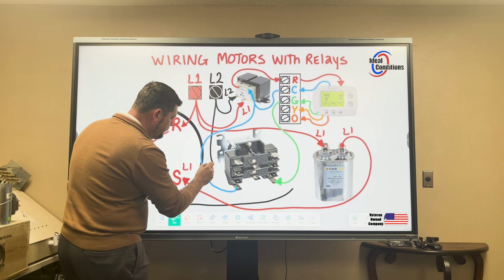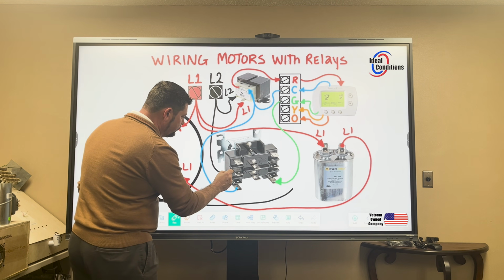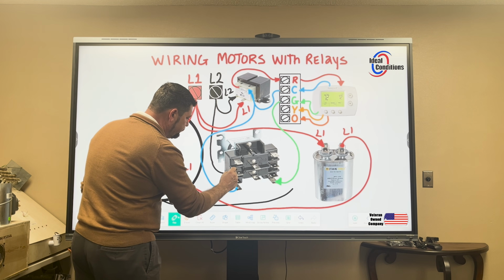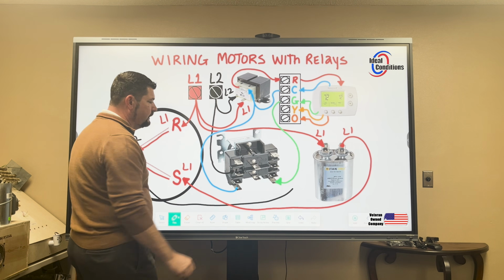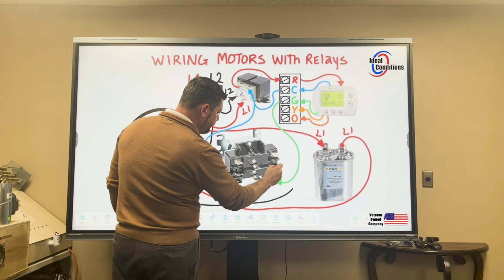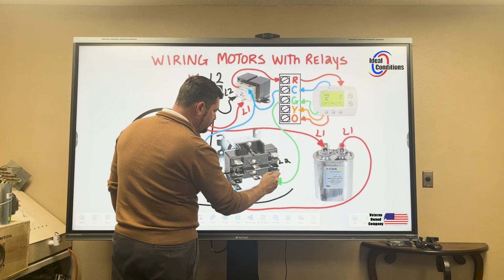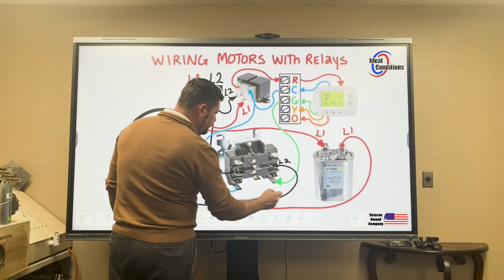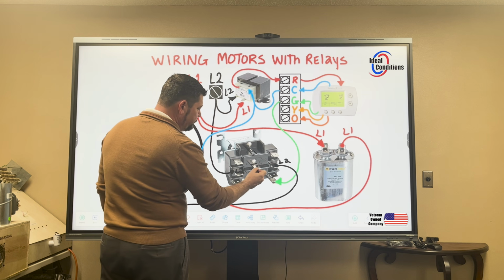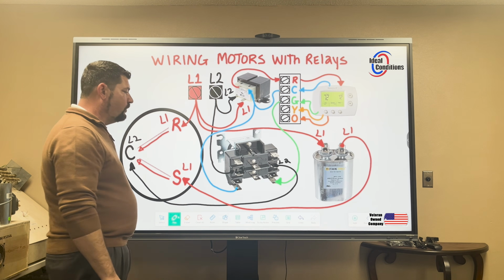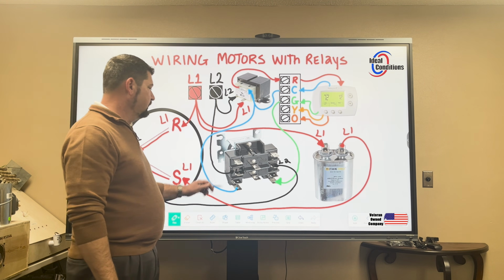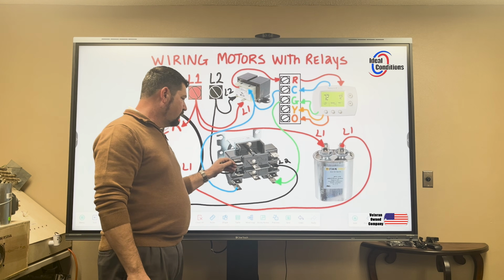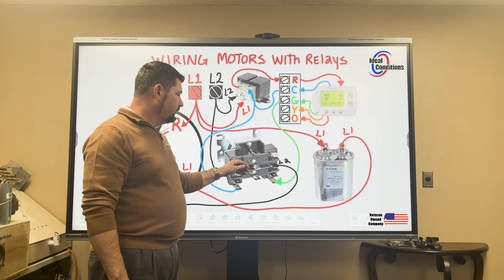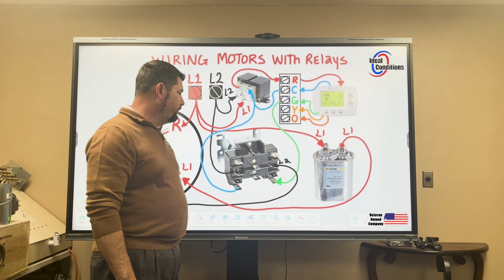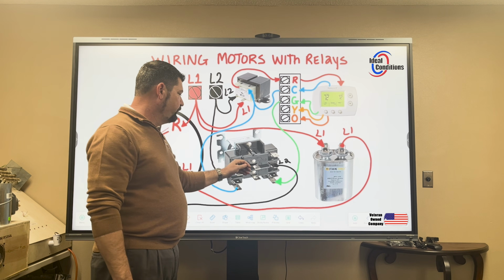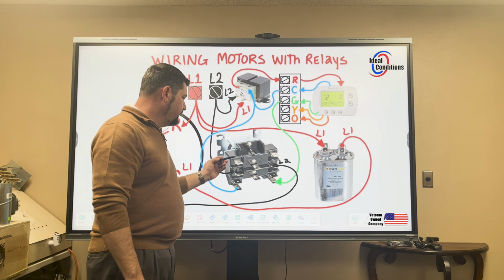So I could put L2 right here, and that means L2 would be present here because I have 24 volts. Because 1, 2, and 3 is a pole all by itself - 1 to 2 is normally closed, 1 and 3 is normally open when I have 24 volts. 2 opens and 3 closes, but it's its own leg.